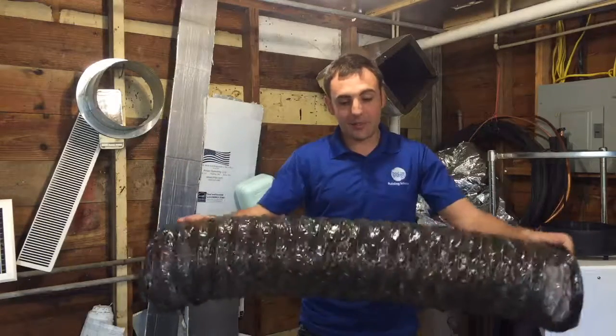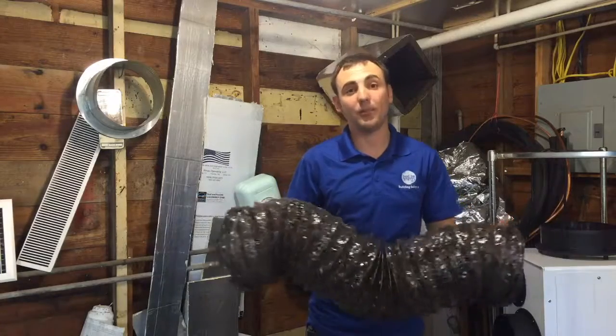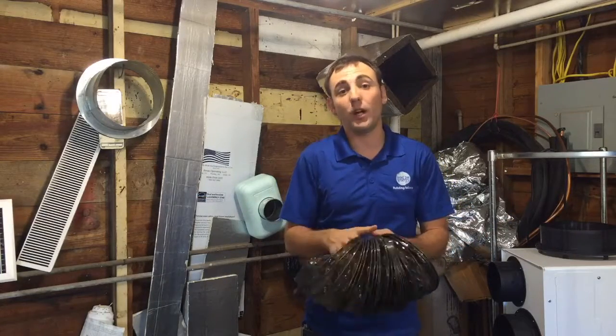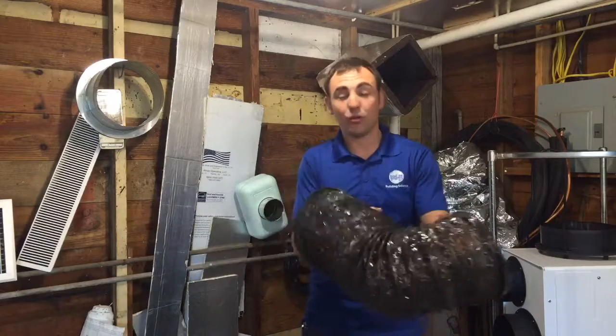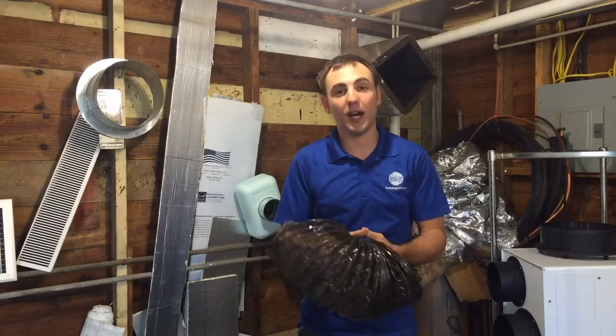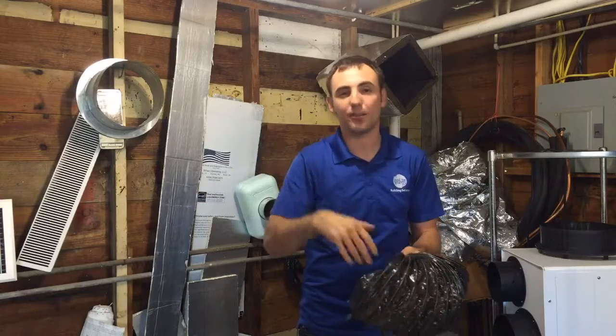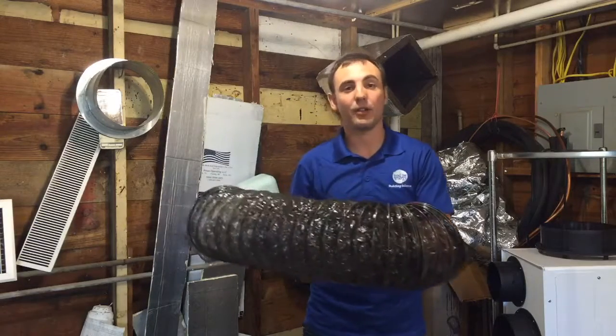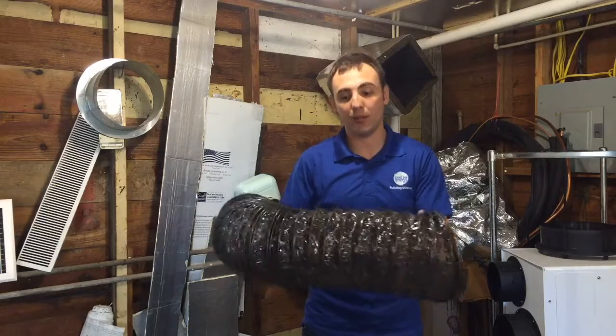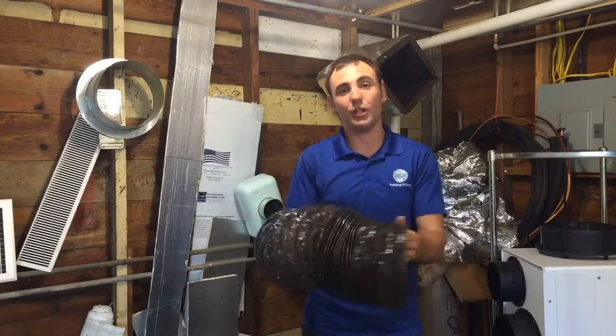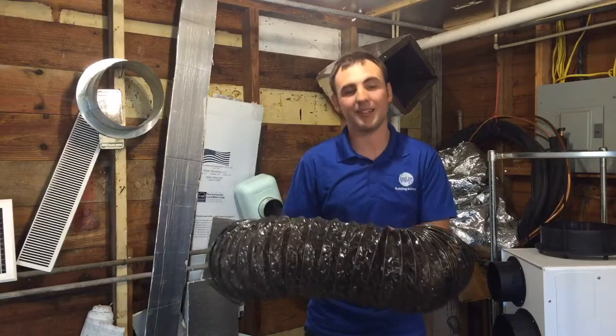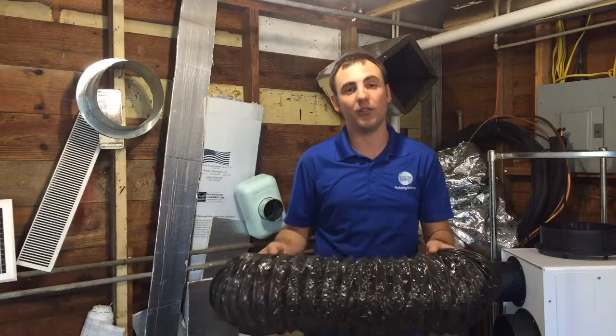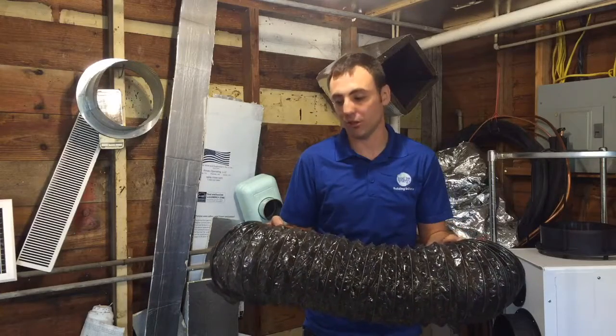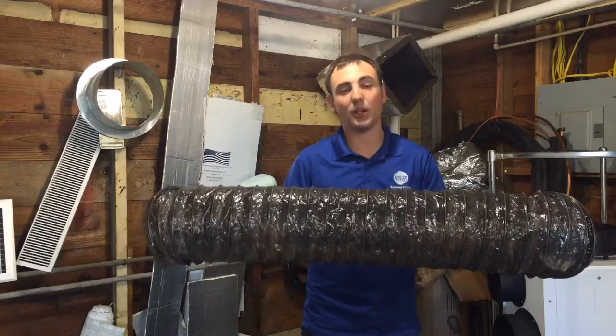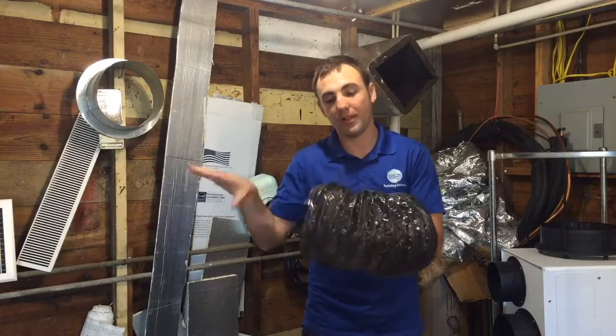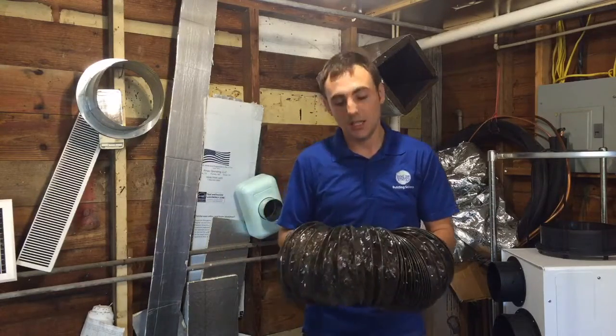So this needs to be stretched as tight as possible, and a lot of times in new construction today it's really difficult, one, to stretch it as tight as possible, and two, to stretch it in a straight line wherever you're going. Sometimes you've got trusses or other attic supports that you're going to have to snake around, so you want to keep those cuts and lines to a minimum. You want to have proper duct design so that you don't have to make a bunch of bends and turns in this, because it's going to ultimately ruin the efficiency of your duct design and system in general. So anyway, this should be stretched apart a lot, otherwise you're going to decrease the amount of air that ultimately gets to the end of the grill.